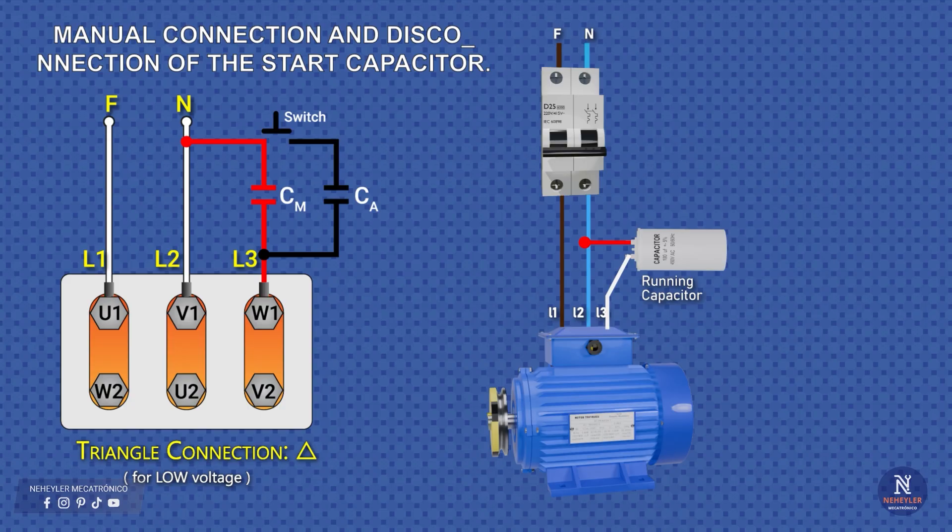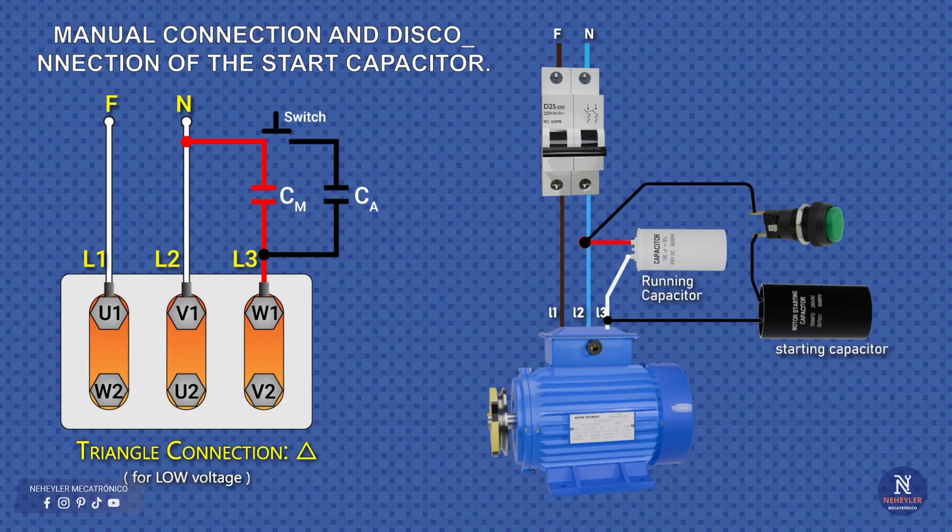Now for the start capacitor. This one should only enter service for a few seconds at the beginning, to provide more torque to the motor. It is connected in parallel with the run capacitor, but in series with the push button. That is, from the third motor terminal we connect to one side of the start capacitor. From the other side of the capacitor we connect to one terminal of the normally open push button. And from the other terminal of the push button we connect to the same junction where the neutral and the run capacitor are.